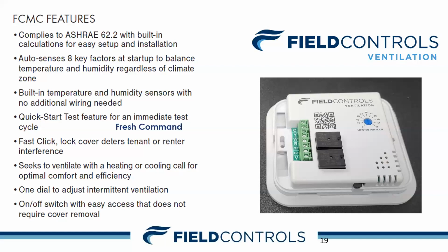The built-in temperature and humidity sensor requires no need to additional wire. So often we see a control with a little temp sensor drilled through a duct or placed outside at a condenser. There's no need for that type of setup because it's already built into the control. So again, speed of install, ease of use, reducing callbacks, all of these are factored into this control. And it has a quick start test feature. So if you see the switch on the bottom, that's an on-off switch. So when you turn it off and you turn it on, it'll immediately boost up into test mode. In addition, if you have this control and you don't want to have ventilation, all you have to do is turn it off.